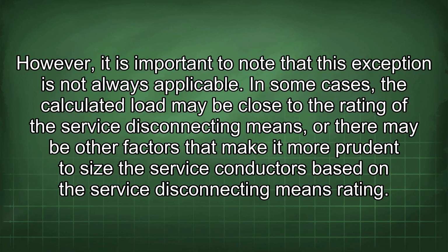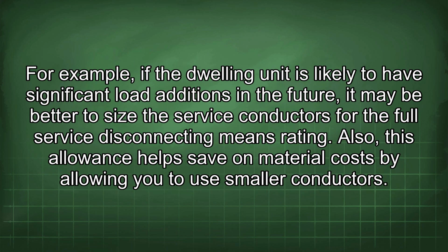However, it is important to note that this exception is not always applicable. In some cases, the calculated load may be close to the rating of the service disconnecting means, or there may be other factors that make it more prudent to size the service conductors based on the service disconnecting means rating. For example, if the dwelling unit is likely to have significant load additions in the future, it may be better to size the service conductors for the full service disconnecting means rating.